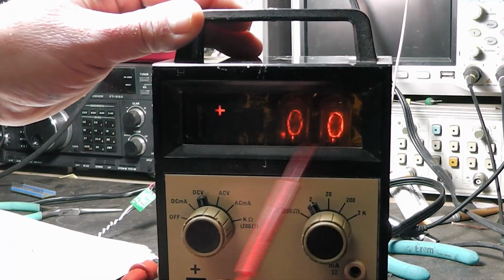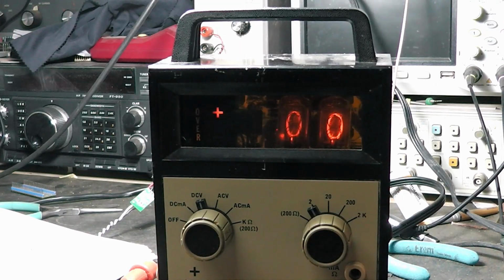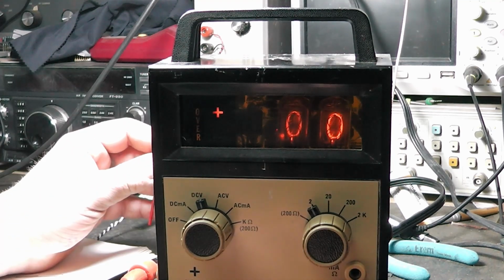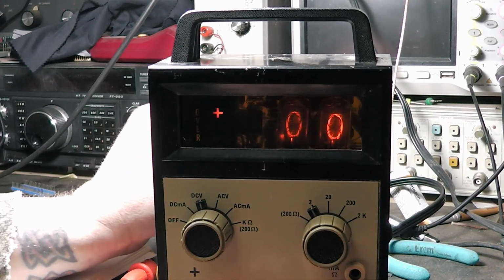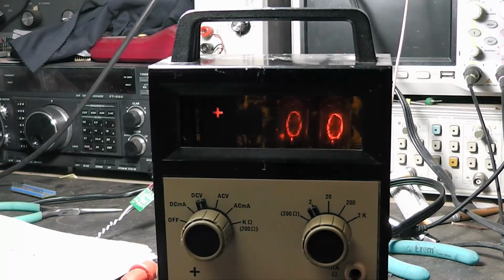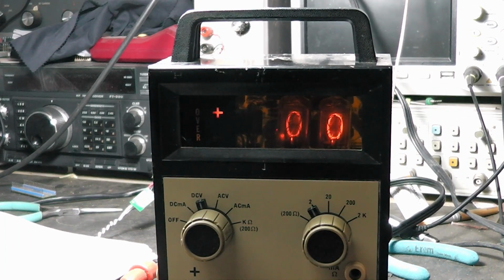You can see the plus sign is lit up, and you've got 2 zeros over there. Use the alignment tool and turn the zero adjust control until the readout is 0.01. Then slowly turn the control until the readout just starts alternating between 0.01 and 0.00. Nothing should be plugged into the jacks at this time. Now I've already done that part too. I went to zero adjust and zeroed it out, and you can see it's holding pretty steady. It's been plugged in for about 2 hours, probably 2.5 hours. I've been doing other stuff and came back over and said, well, I better shoot this video.